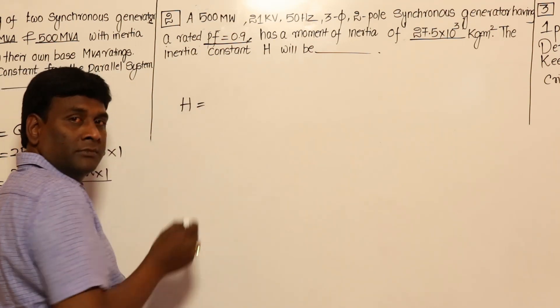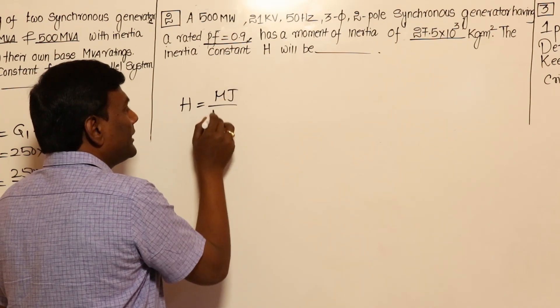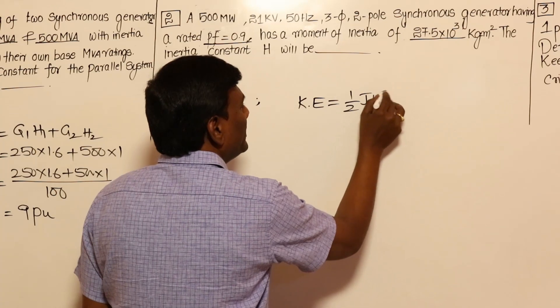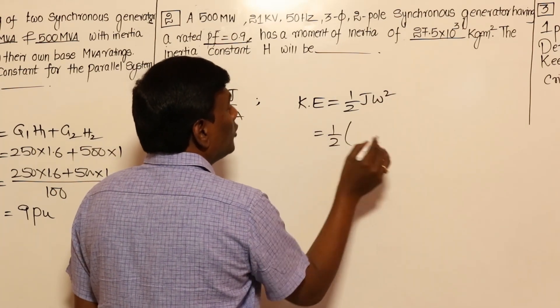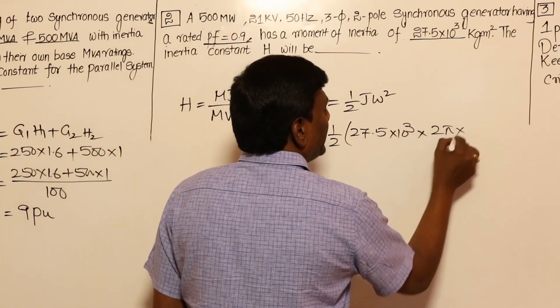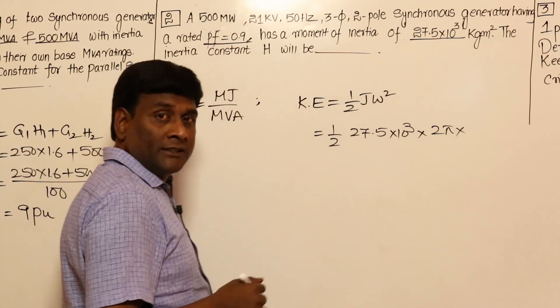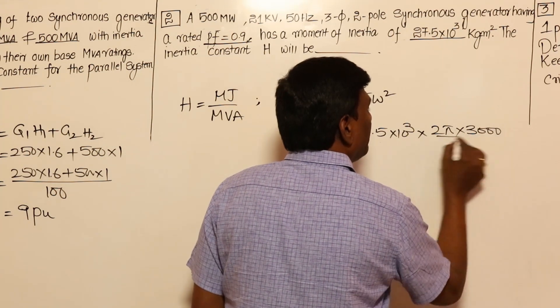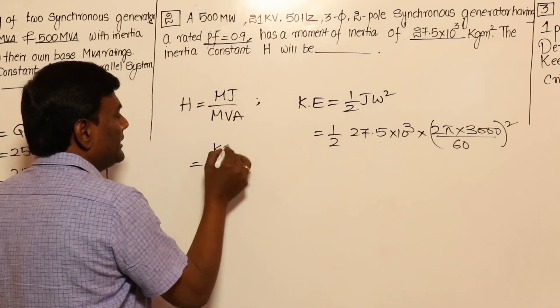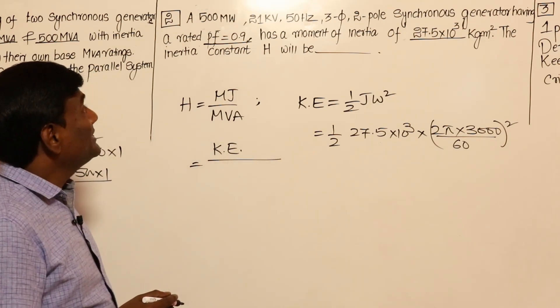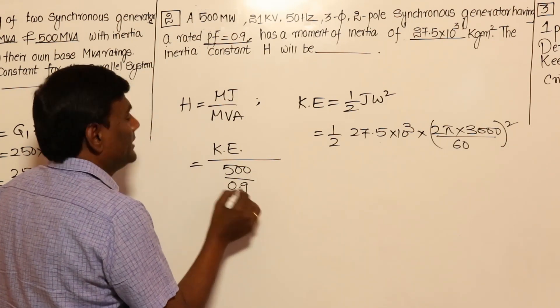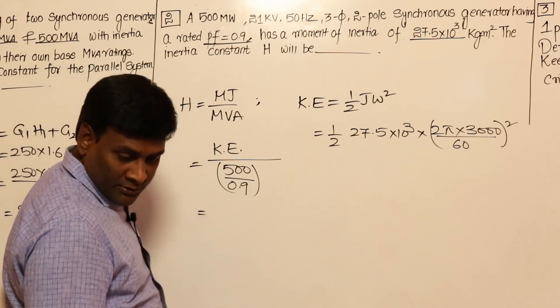The definition of inertia constant H is in MJ per MVA. We have to calculate kinetic energy: KE = ½Jω². So KE = ½ × 27.5×10³ × (2π × 3000/60)², since for a 2-pole 50 Hz machine, speed is 3000 RPM. Then H = KE divided by MVA, where MVA = 500 MW / 0.9 power factor. I got an answer of 2.442.